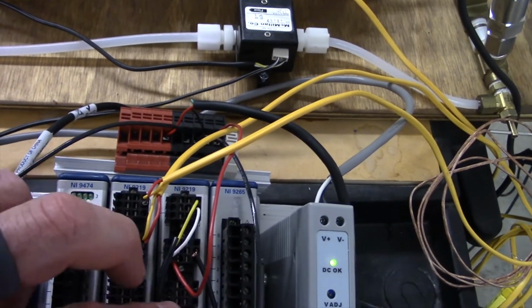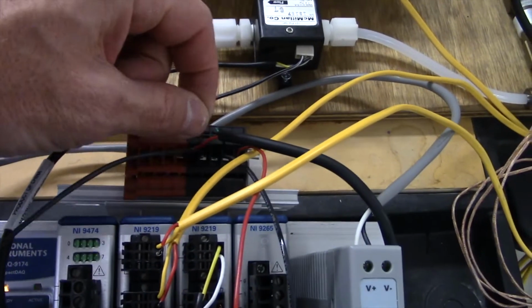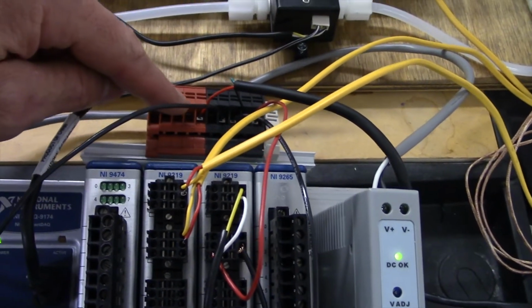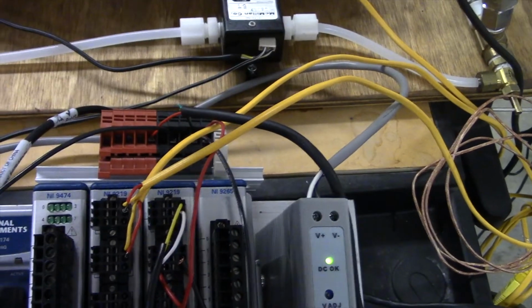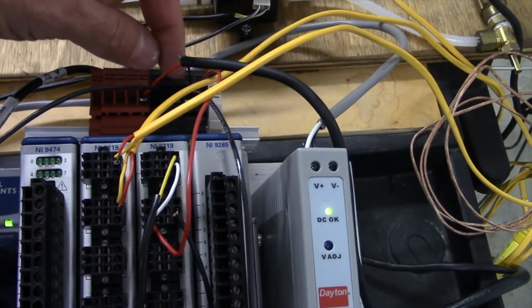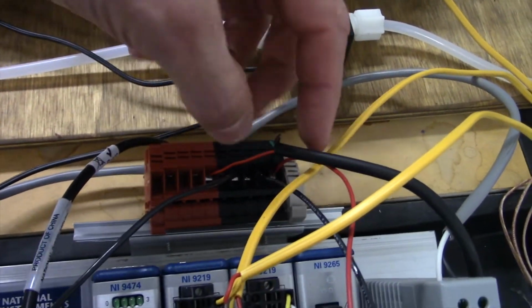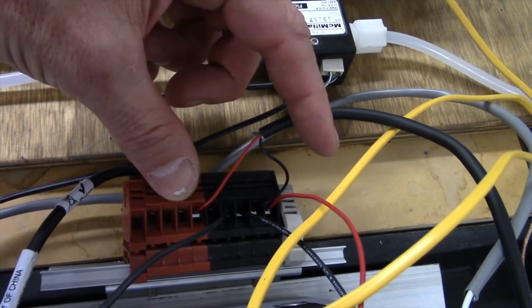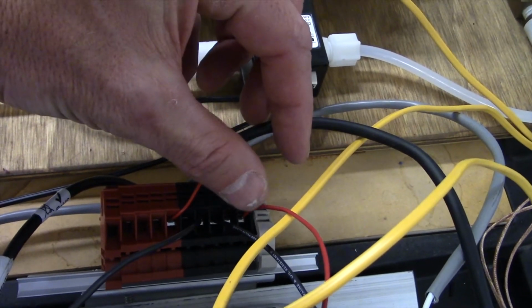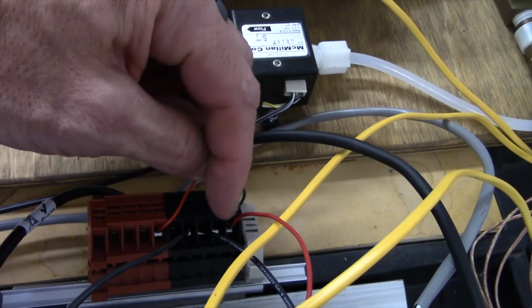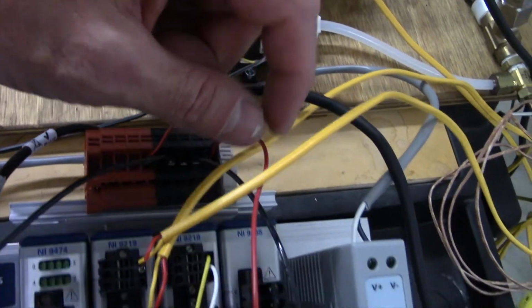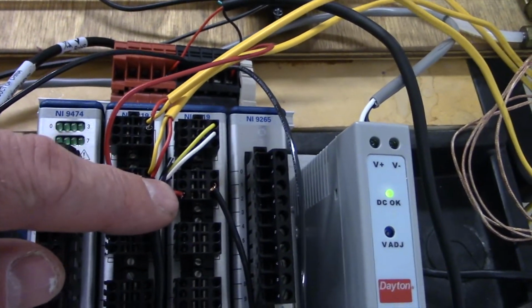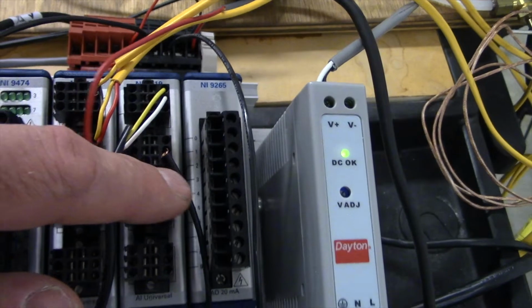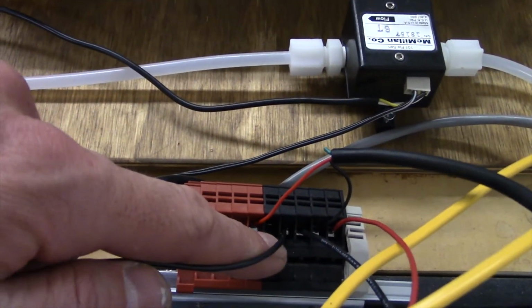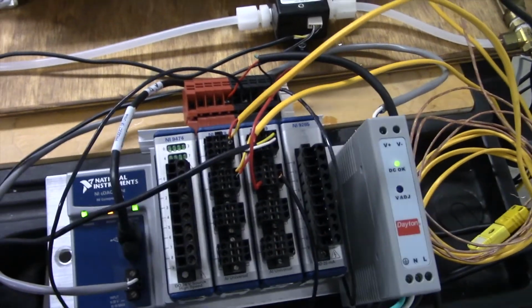they call it a loop measurement. So here is the power, this red. Positive from the power supply is powering the device, goes in there and then comes back out. Then these two wires are connected. I'm not sure you can see that very well. Here's the positive going to the positive power supply. Here's the negative, and these two ports are connected on the back here, so it's as if they're in the same port. Then this wire comes here into the positive supply for the data acquisition. Then the negative is going back into our negative power supply here. Power to the pressure sensor to the data acquisition. So it's one series loop.